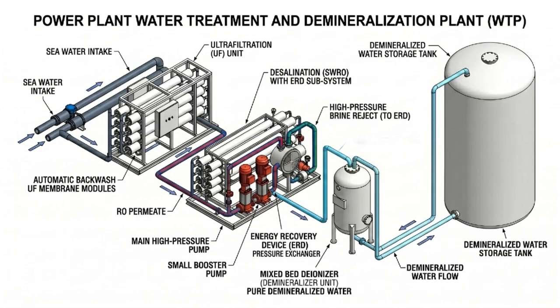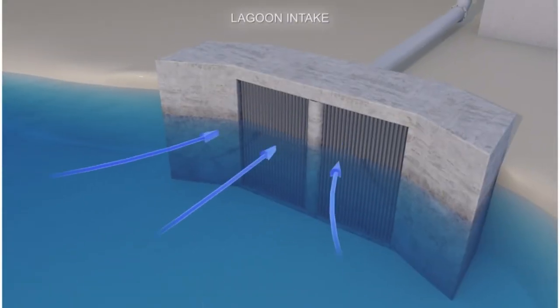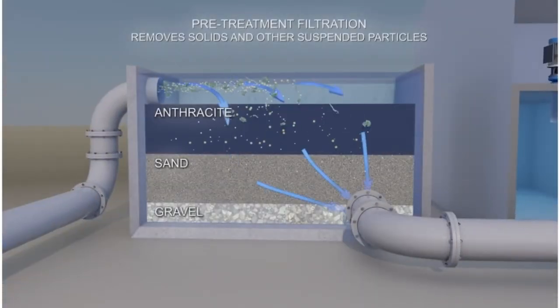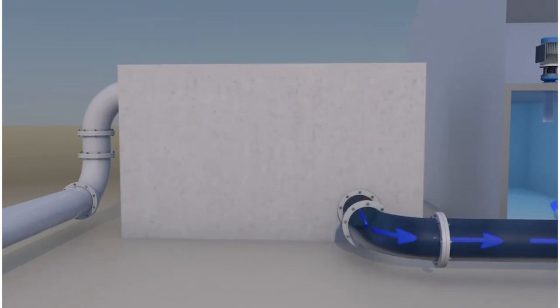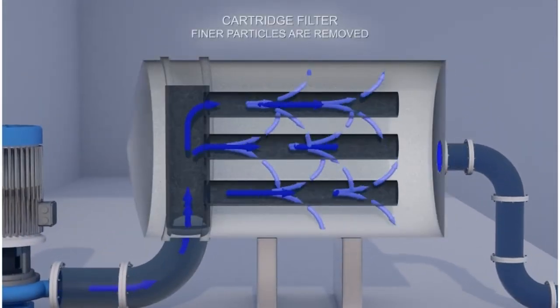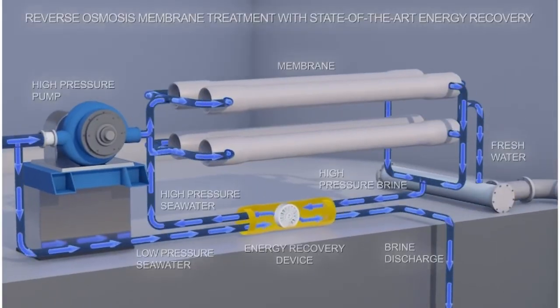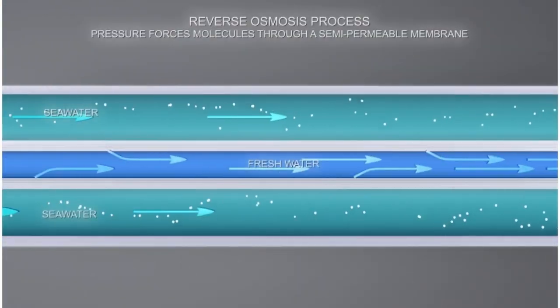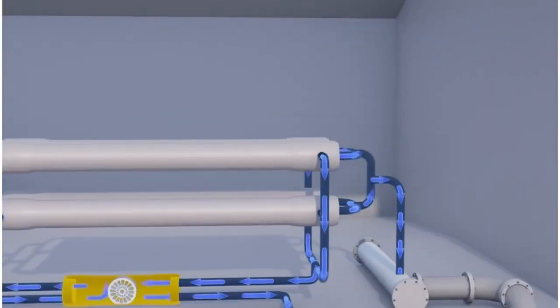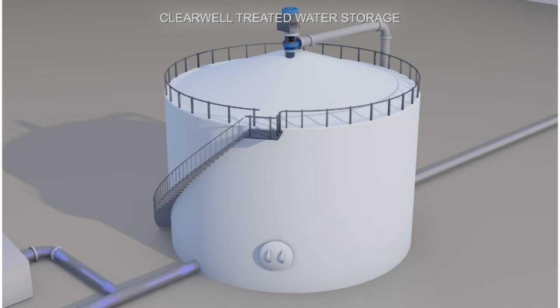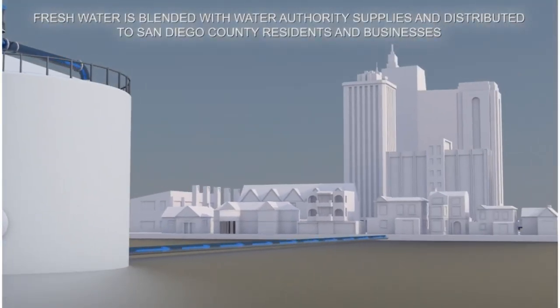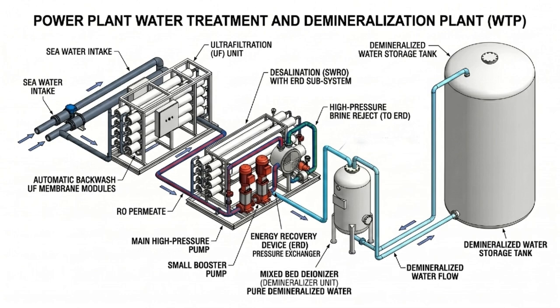To support the engine cooling system, the plant utilizes a dedicated water treatment and demineralization plant to produce high-purity water for the closed cooling loops. Raw water first passes through ultrafiltration and reverse osmosis systems to remove suspended solids and dissolved salts. The water then enters the demineralization stage, where remaining minerals and ions are removed before being stored as demineralized water. This high-quality water helps protect the cooling system from scaling, corrosion, and long-term performance degradation. With the fuel, air, and cooling systems covered, let us move to the final supporting utility, the lube oil system.